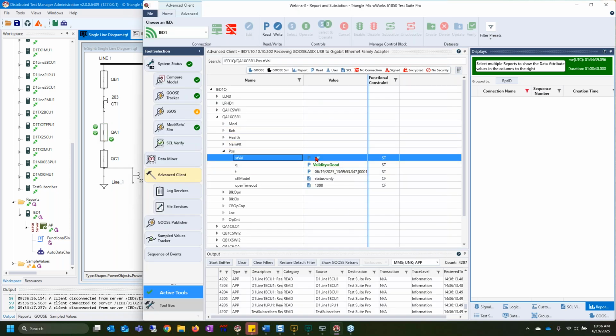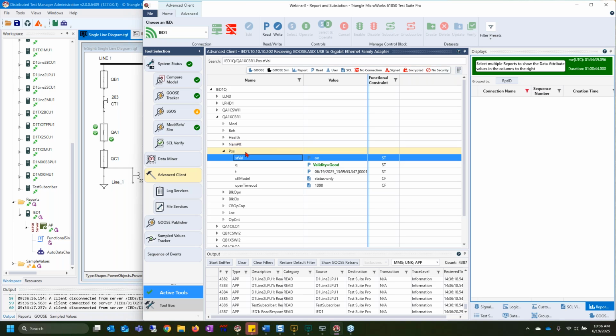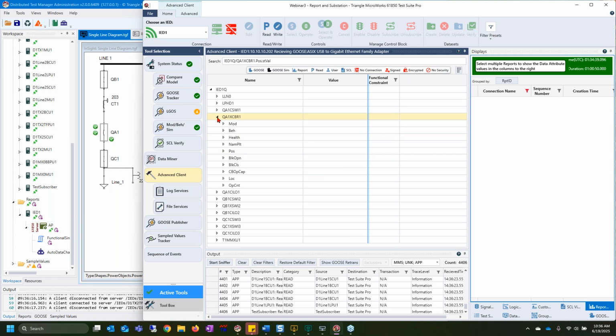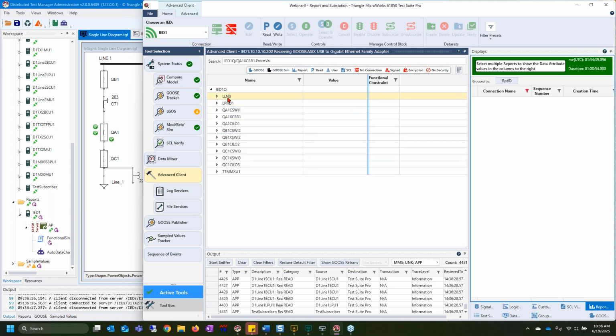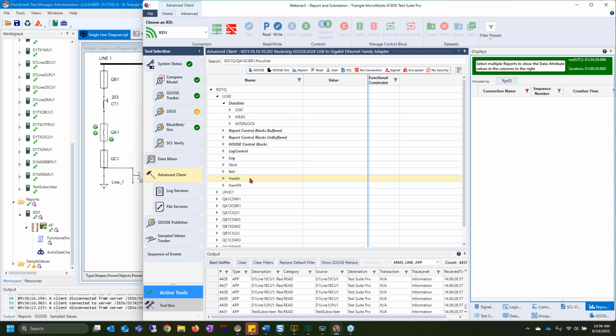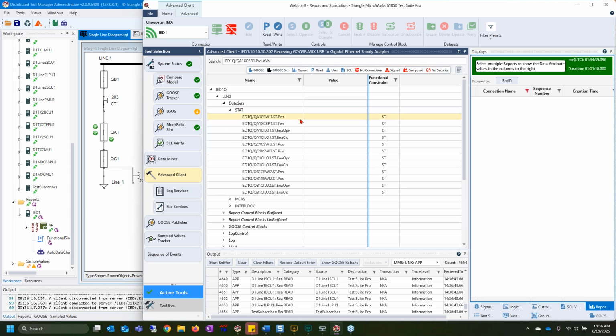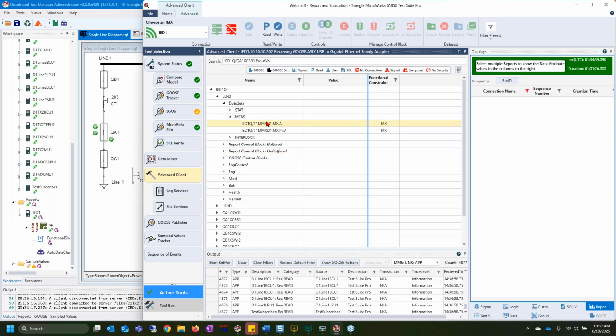So if I go ahead and close this back, I can do a read and that'll all change. But let's go ahead and take a look at buffered and unbuffered reports like Jackson was talking about. So we'll go up to LLN0, which is a required logical node. And inside of there, we can see a data set. I have three different data sets inside of this model here that the server knows about. We've got the stat, that stands for the status values, and I can open that up and see that we've got the CSWI, so a controllable switch, status value, the position, XCBR, all sorts of the functional constraint ST data being used in this data set, as well as a measurement data set. It looks like a lot less, but that's because we're stopping at the data object level here.